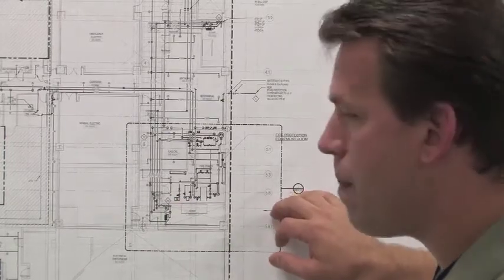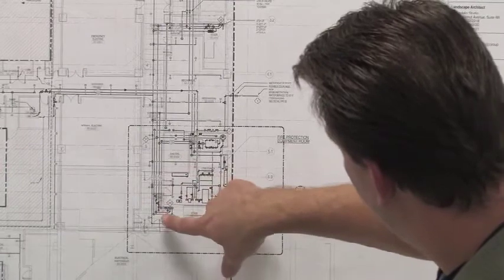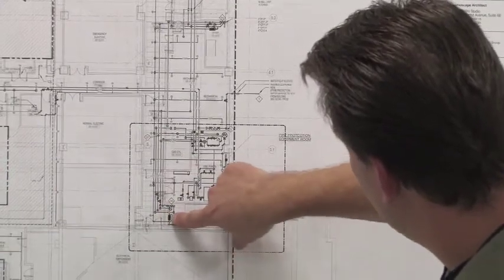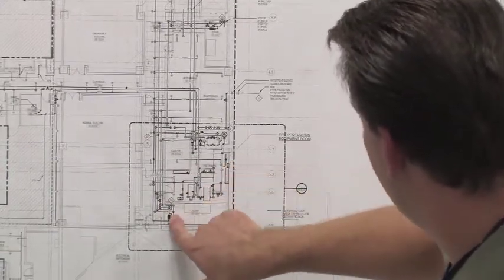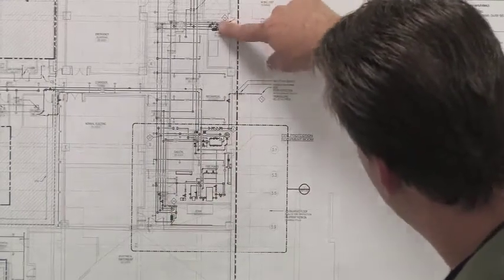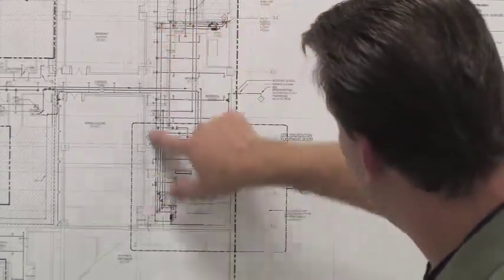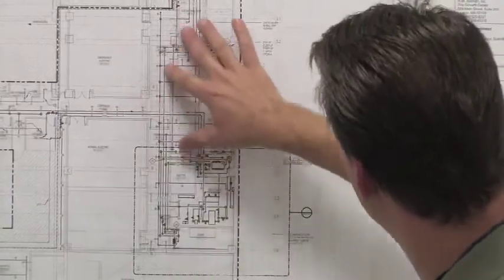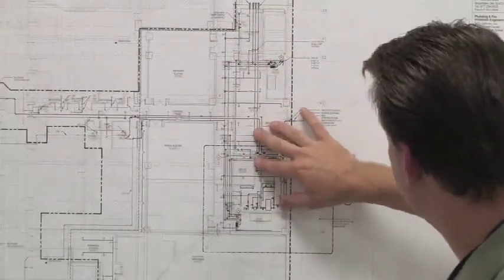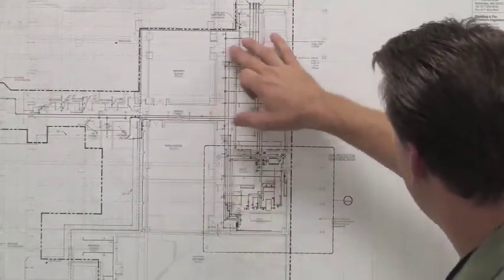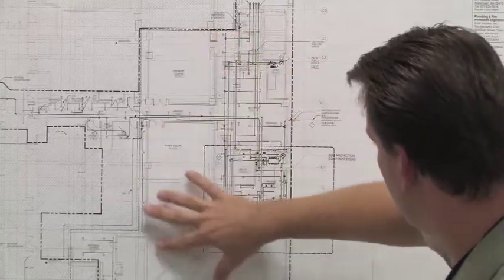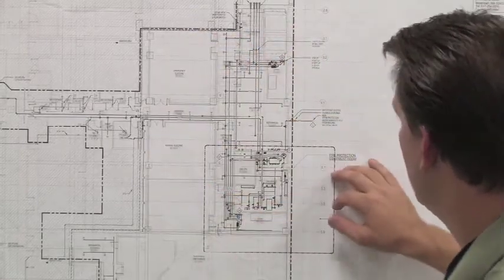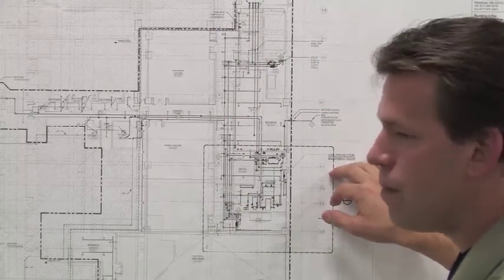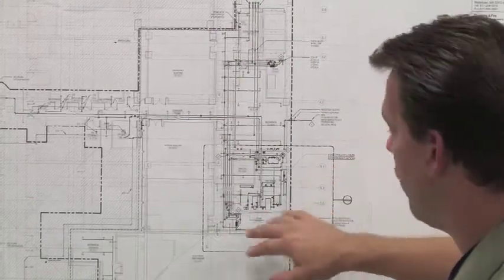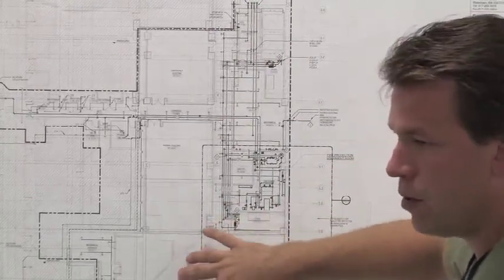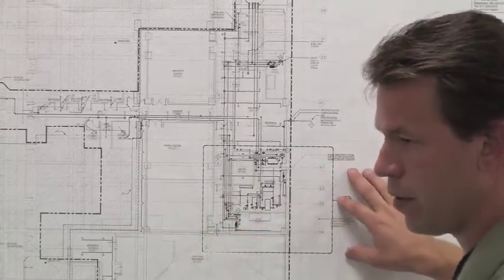Where do we get the dual feeds? There's a floor control valve station in this stair, and one in this stair here. They basically just feed the mechanical spaces in the public area, based on the fact that most of this floor is electrical. So do we have a pre-action in the electricals? No, the vaults don't have sprinkler. The vaults have no sprinkler whatsoever? The vaults have no sprinkler.